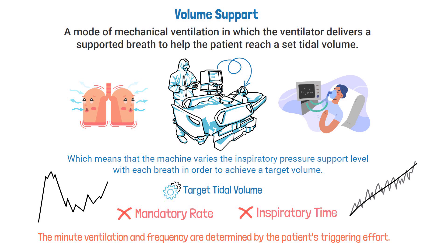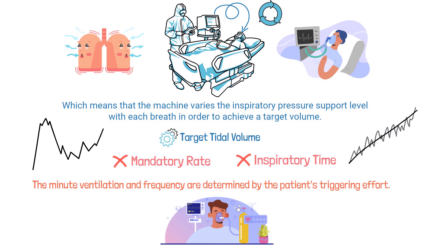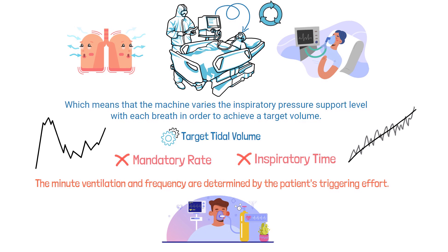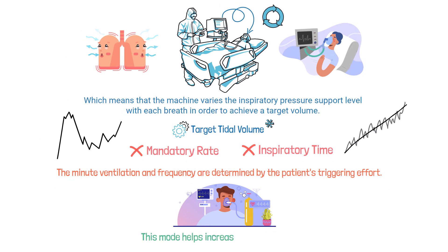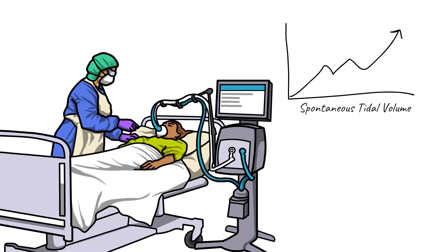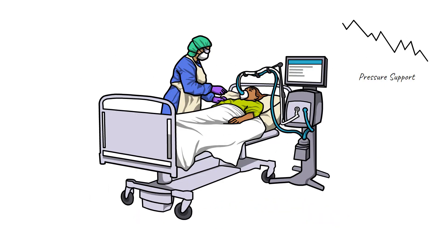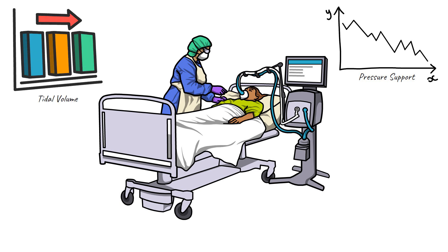This mode is not quite as common as some others, however it is often used to wean patients from anesthesia. It's effective because this mode helps increase patient comfort. For example, when a patient begins to wake up from anesthesia, their spontaneous tidal volume naturally begins to increase, and the ventilator automatically reduces the level of pressure support so that the tidal volume is maintained.